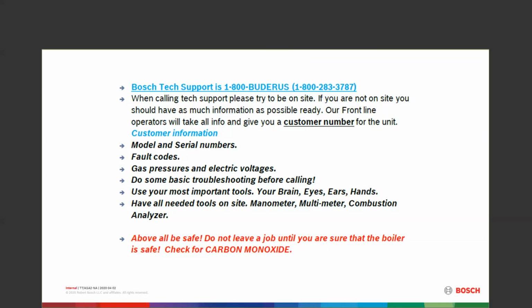So make sure you leave it safe. Check for carbon monoxide. All of our products require under 200 parts per million in the venting. In addition to that, check around. Check the cabinet. Make sure there's no gas leaks, that type of thing. But make sure your job is safe. You're the last guy that worked on it. And know that. It's your responsibility to tie it up and make sure everything is correct.